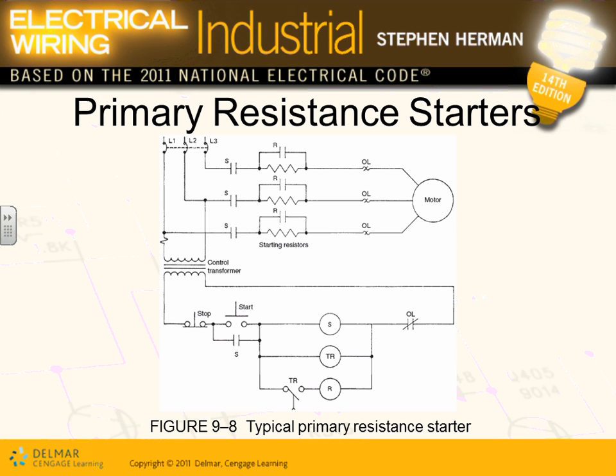When it comes to any motor, when you put any machine online, there are 3 things you need to worry about. Number 1, starting torque and the starting current. If the starting current is so high, you can kill the electrical system, dim the whole system. That's a starting current. We need to reduce it. The other one, guys, is starting and stopping the motor or reversing it, that's another thing you need to worry about. And speed control. You need to be able to control the speed of the motor.